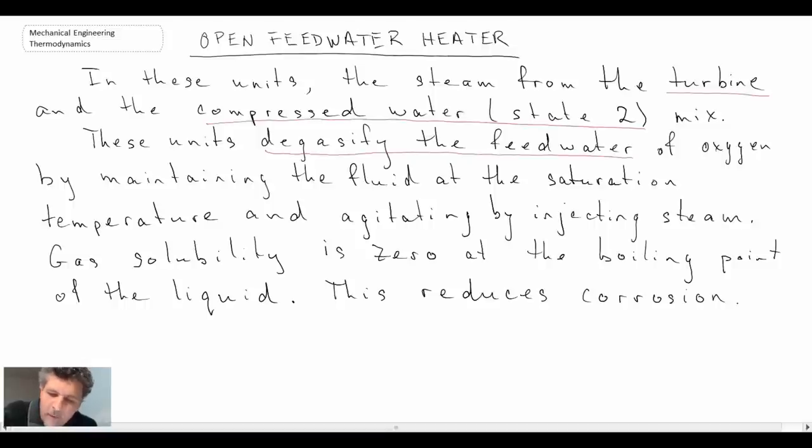Remember we talked about saying that you can have corrosion within your boiler due to oxygen being present within the feed water. And with the open feed water heater, by agitating through the injection of steam, we're able to liberate some of that oxygen or air that might be in the boiler feed water. Consequently through this process we reduce corrosion within the boiler, which is an important thing that we want to be able to do.